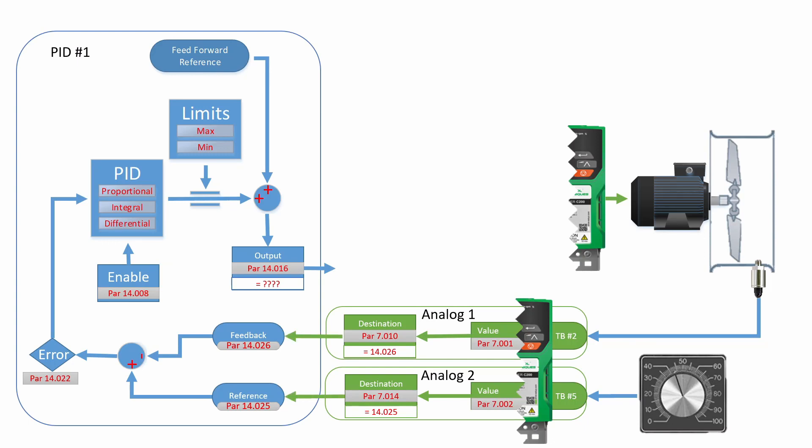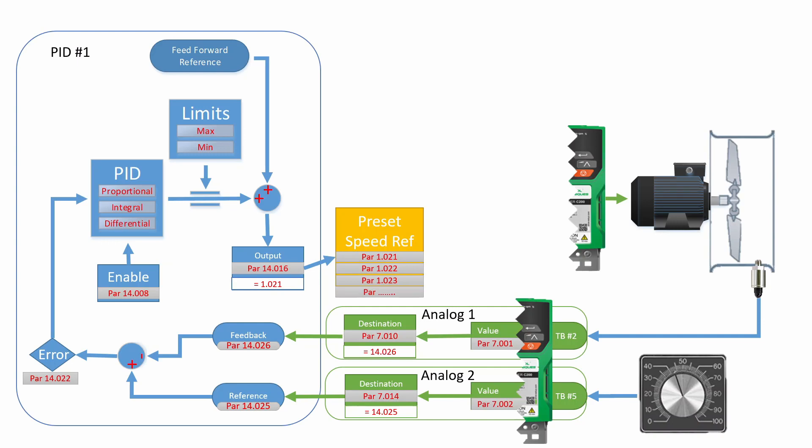So what we need to do now is map analog 1 to the feedback and map analog 2 to the reference of the PID block. To do that, all we do is type in the parameter number in the destination blocks. The input side of the PID is now complete. As you can see, the output of the PID loop is not set up, indicated by the question marks.